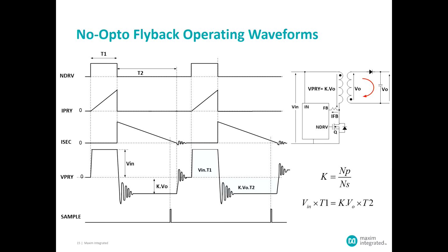As the current gets down close to zero, we still have the output voltage, but with almost no current flowing through the secondary. So we have the best and most accurate representation of the output voltage transformed over to the primary. We sample that voltage on the primary at that point in time, just before the current reaches zero on the secondary, while the induced voltage from the secondary is still sitting on the primary.